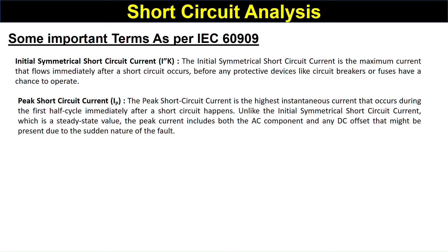The Peak Short-Circuit Current is the highest instantaneous current that occurs during the first half-cycle immediately after a short circuit happens. Unlike the Initial Symmetrical Short-Circuit Current, which is a steady-state value, the peak current includes both an AC component and a DC offset that may be present due to the sudden onset of the fault. It has two components: the AC component and the DC component.